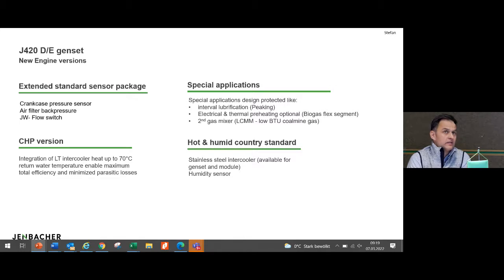We have also implemented an enhanced service sensor pack in the new versions. This means we have standardized the crankcase pressure sensor and air filter back pressure measurement, and to see whether we are cooling or post-cooling the turbocharger, we have implemented a jacket water flow switch. We have also implemented a new CHP version with up to 70-degree return temperature as a maximum on the low temperature side of the intercooler, which maximizes the total efficiency and minimizes the parasitic losses.